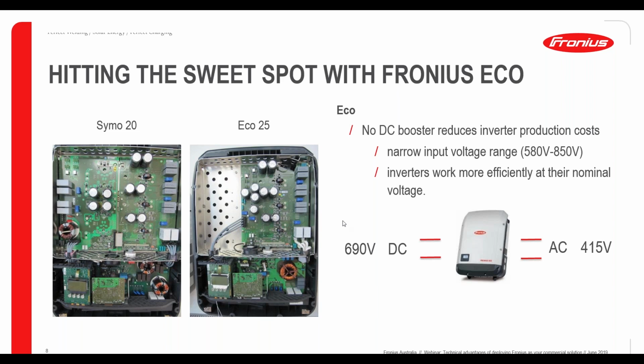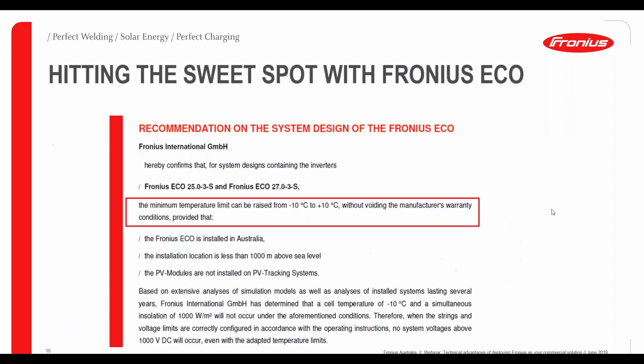So in terms of that, it's important to realise that with this singular tracker, as well as the limitation of the DC voltage window that the Eco presents, we do have a particular recommendation for the Fronius Eco inverter only. It's important to realise that when you're dimensioning these systems, there are typically a lot of different ways to try and work out exactly what your minimum panel temperature is going to be.